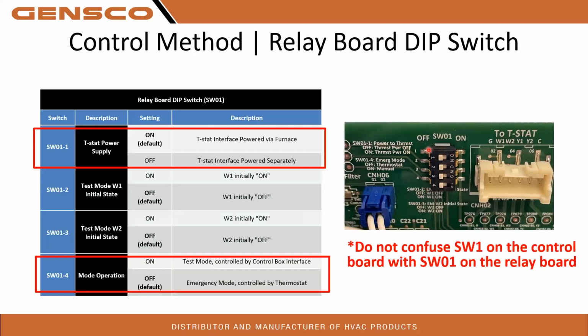This is that little dip switch I was just talking about, SW01 on the relay board. Again, this is the settings to set up the test mode operation. One thing that's important is SW01. This is what powers your 24-volt thermostat. If that is in the off position, you will need a 24-volt transformer to power your 24-volt thermostat. If you turn it to the on position, it will get its power from the furnace.